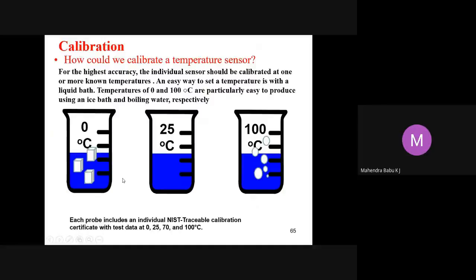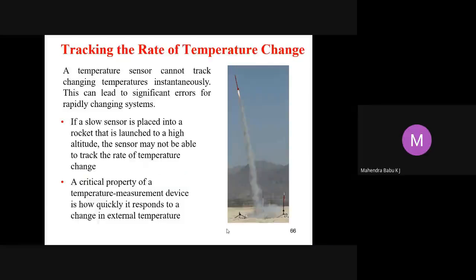So, calibration. How could we calibrate the temperature sensors? For the highest accuracy, the individual sensor should be calibrated at one or more temperatures. An easy way to set the temperature is with a liquid bath, where temperatures of 0 and 100 degrees Celsius are particularly easy to produce using an ice bath and the boiling temperature of water. Each probe includes an individual NIST traceable calibration certificate with test data at 0, 25, 70 and 100 degrees Celsius.